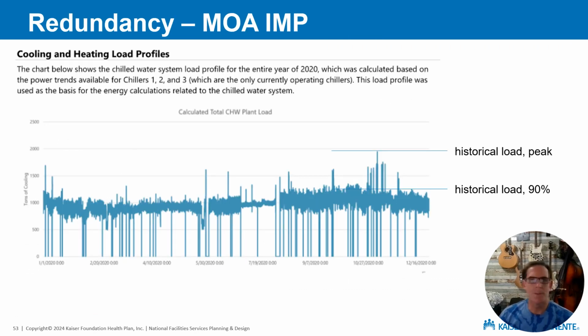So we have to talk about this for HVAC folks. We have to actually talk about sizing for the load and that partial capacity, because partial capacity at one equipment failure can often mean very good capacity at equipment failure. So to look at this example here, we have a historical peak load that's just under 2,000 tons. That's the actual peak load. But we have a whole lot of time in this system where it can be run at 1,000 tons. And the 90% load is somewhere in the neighborhood of 1,200 tons.